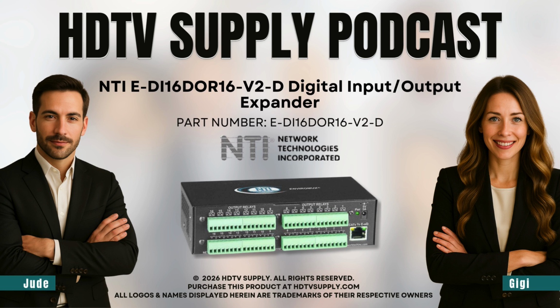Which is critical. And here's a surprising little detail I found. One of those inputs is very specific. That's right. One dedicated pair is a tachometer input. For what? Measuring fan speed? Fan speed, pump speed, anything that rotates. It can measure from 0 up to 255 hertz. It's a really smart inclusion. And the physical reach here is pretty wild. We're talking cable runs up to 500 feet. 500 feet, yeah. About 152 meters. Using standard CAT5 cable. So you can cover a huge area like a massive data center from one central point.